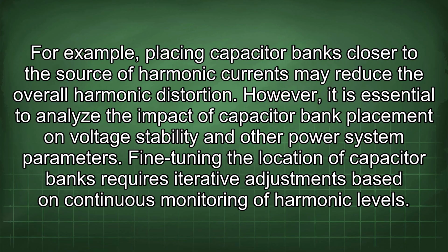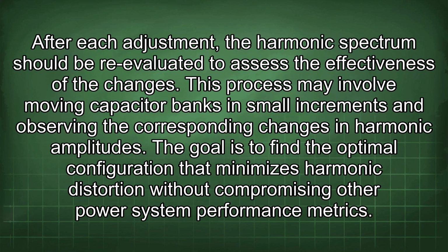Fine-tuning the location of capacitor banks requires iterative adjustments based on continuous monitoring of harmonic levels. After each adjustment, the harmonic spectrum should be re-evaluated to assess the effectiveness of the changes. This process may involve moving capacitor banks in small increments and observing the corresponding changes in harmonic amplitudes. The goal is to find the optimal configuration that minimizes harmonic distortion without compromising other power system performance metrics.